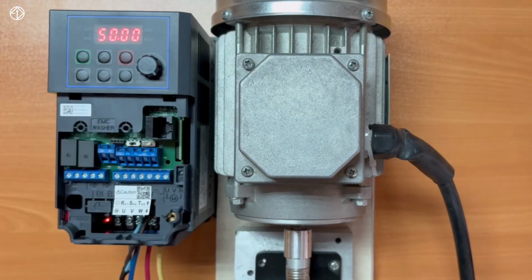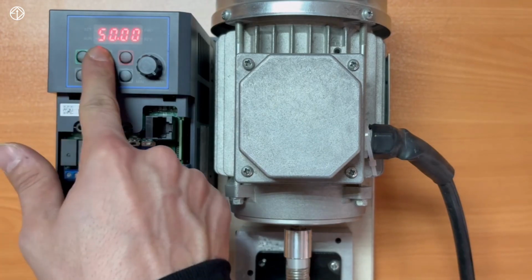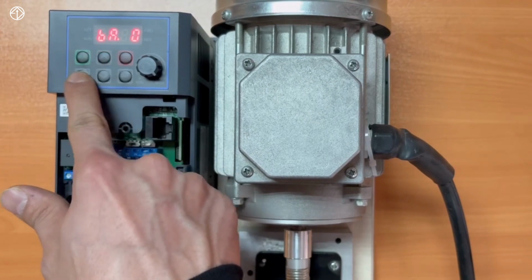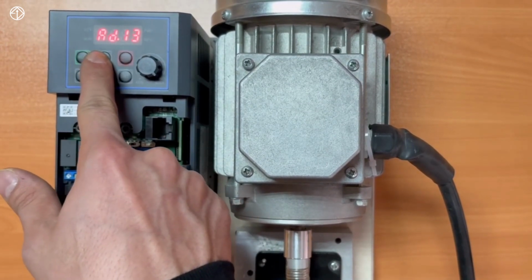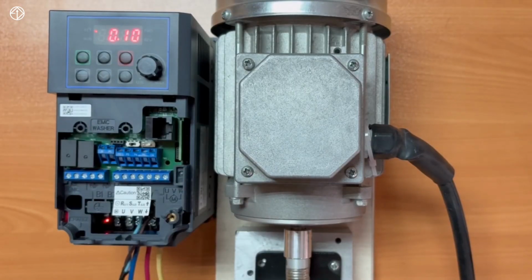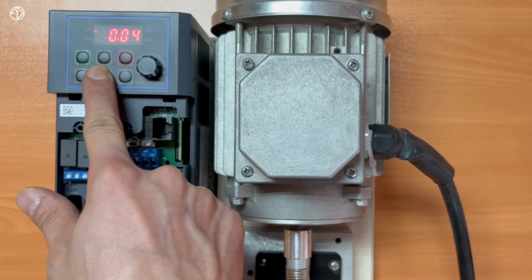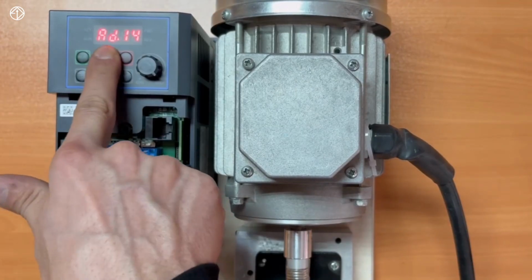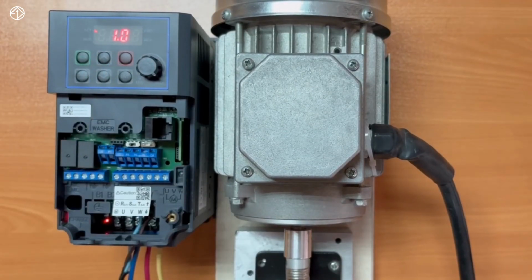The second method we mentioned is through DC braking. We said that a DC current, based on the rated current specified in the parameters of the electric motor, is injected into the motor winding and immediately locks the shaft of the electric motor, stopping it. For this, we said you set parameter Ad.8 to the value 1. For parameter AD14, which is the time before applying the DC current, we set it to 0 because we want the DC current to be injected immediately.